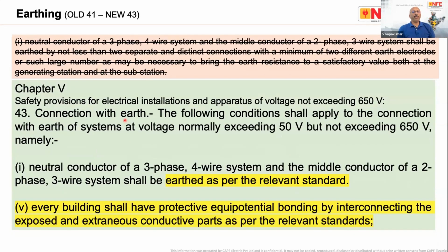Today's subject is mostly about automatic disconnection of supply. That means, in case of any fault, how to disconnect the supply, what the modern methods are to disconnect the supply, and what modern testing instruments are available to ensure automatic disconnection of the supply. But please note that it is from regulation 43. The old regulation was 41, but the new regulation is number 43.